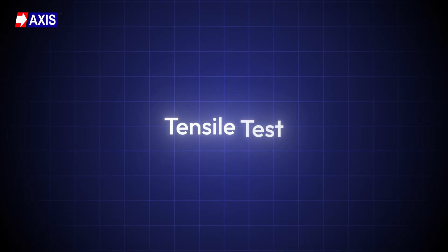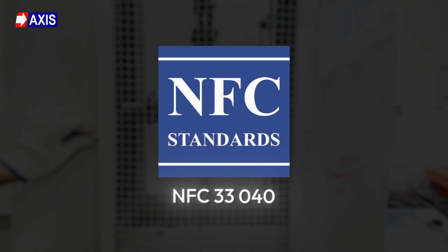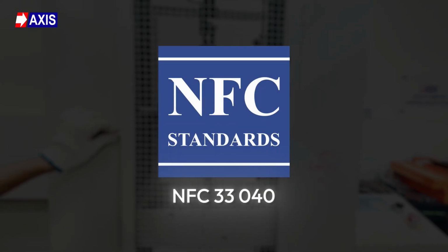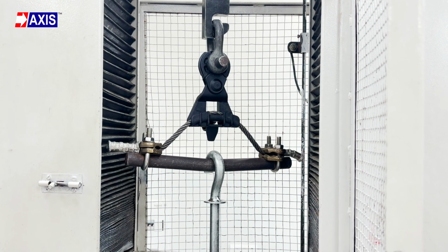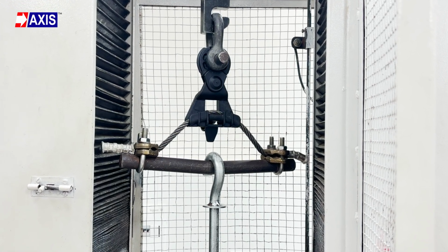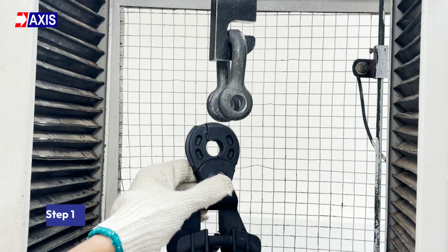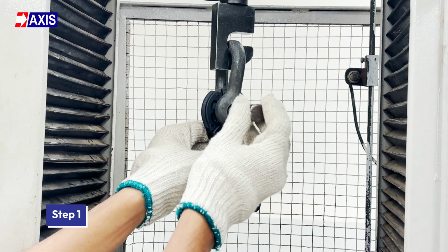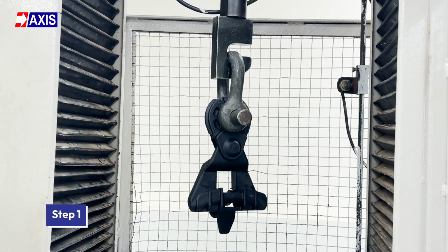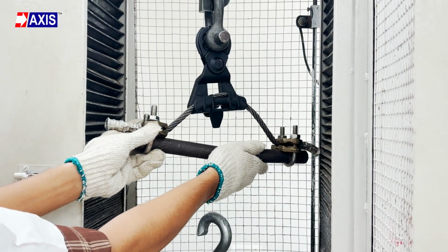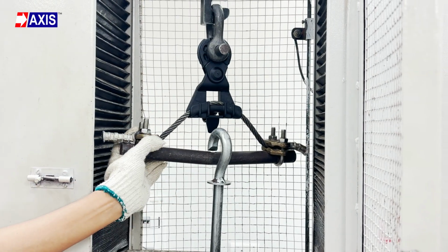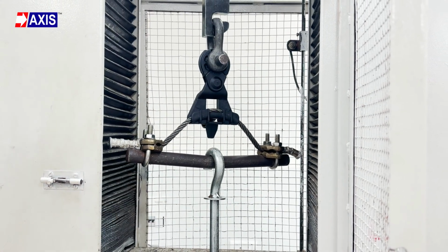Lastly, tensile test as per NF C 33040. This test checks the mechanical strength of your suspension clamp under full tension. Step 1. Mount the clamp in the tensile testing machine with the load aligned to the clamp fixture. Tighten the grips and ensure it is securely held in the fixture.